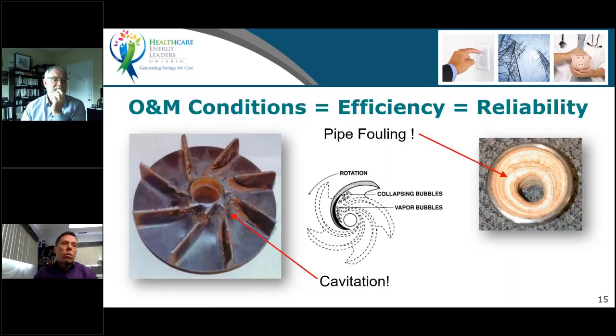If you don't have a pump curve, you can actually build one by a simple test, and you can figure out where you are on the pump curve if you're far off that best efficiency point. Now, sometimes pump curves change, and they change because the pumps change. On the left-hand side here, we see an impeller that looks like it's being eroded by particulate matter, but in fact, it's being cavitated by the water flashing to steam because the pressure conditions aren't right at the inlets of the pump. So you get these bubbles of vapor that form in the water.